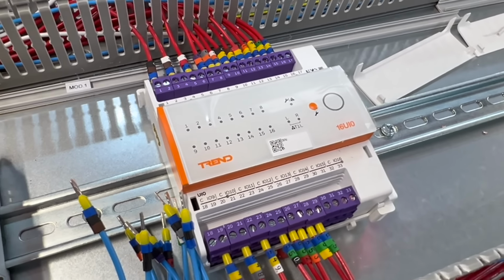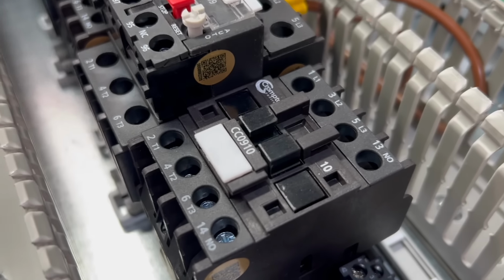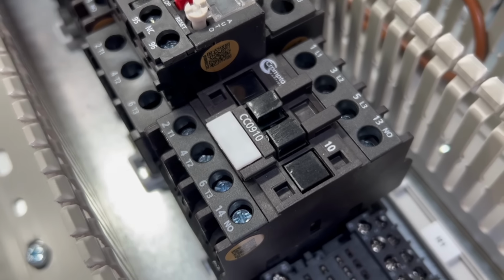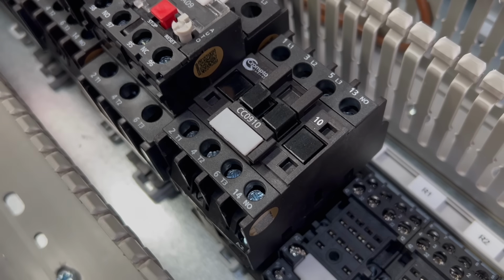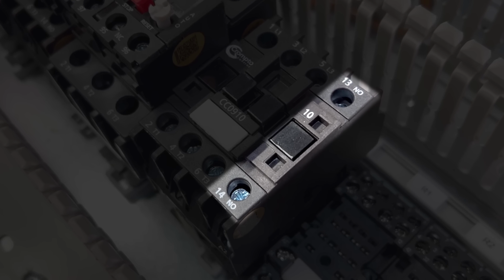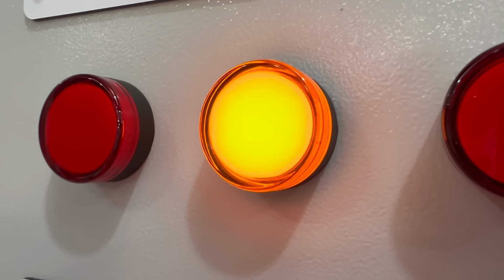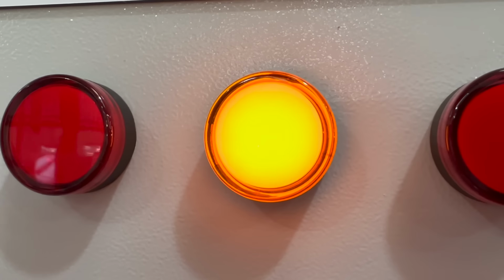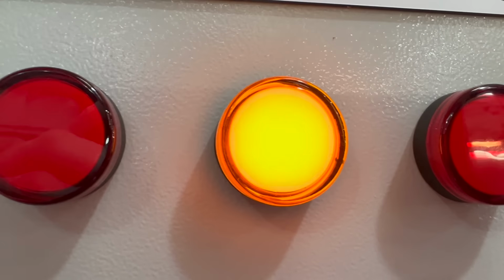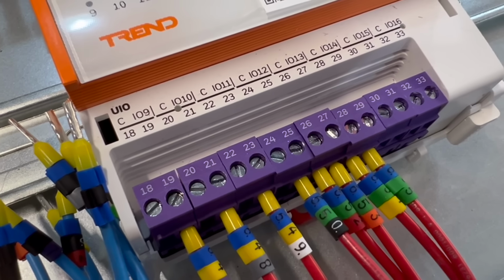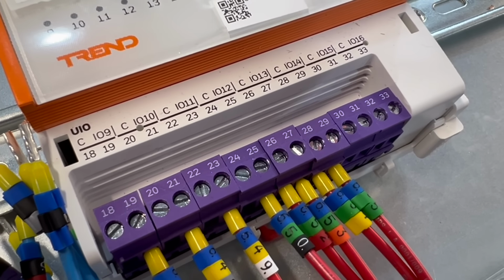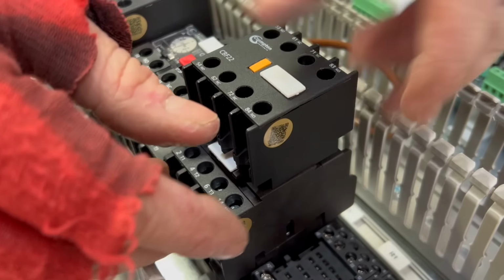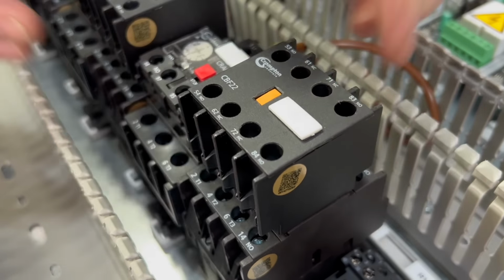Also connected to communicating with the DDCs are the auxiliary contacts on a contactor. Most contactors will have an additional pair of contacts that aren't rated to switch the main loads, but rather are used for signalling purposes. So they might do something as simple as switch on a lamp to show that the contactor is closed and a certain load should be operating, or connect to an input on a DDC to tell the system that the load is operational.